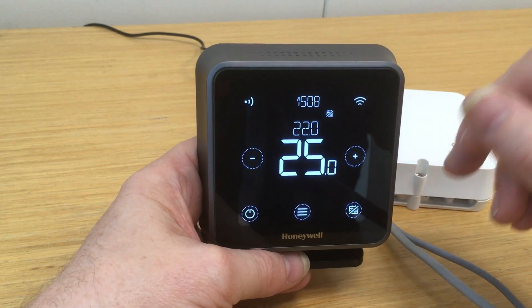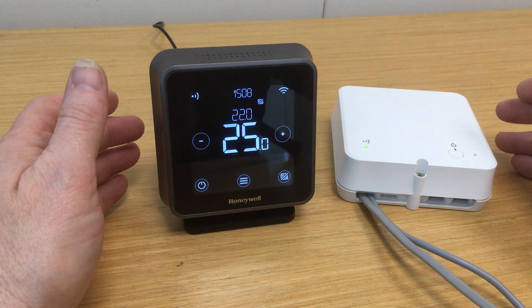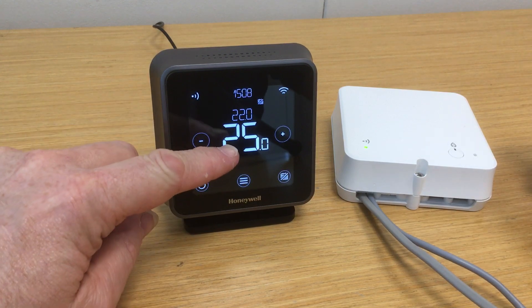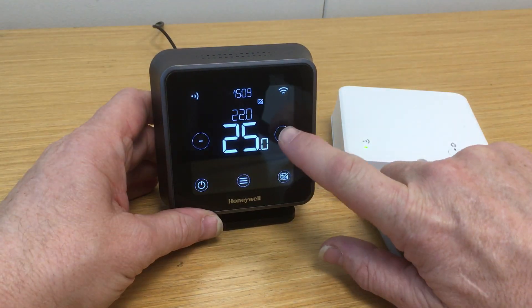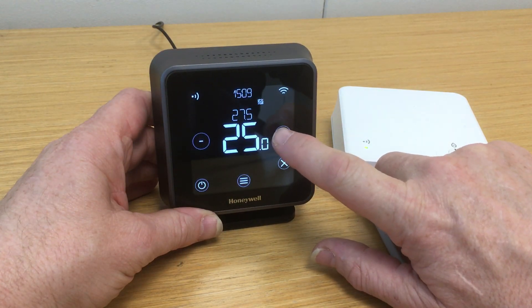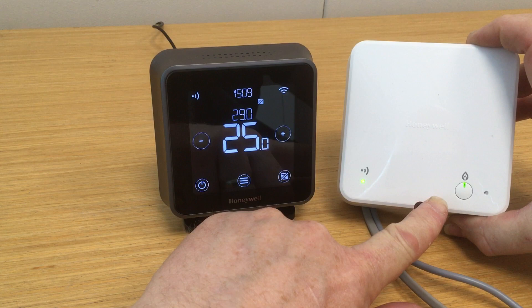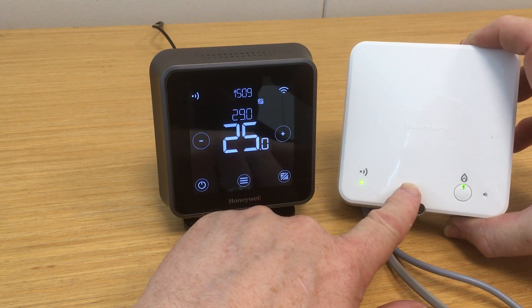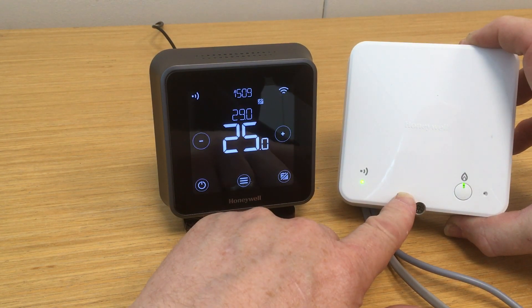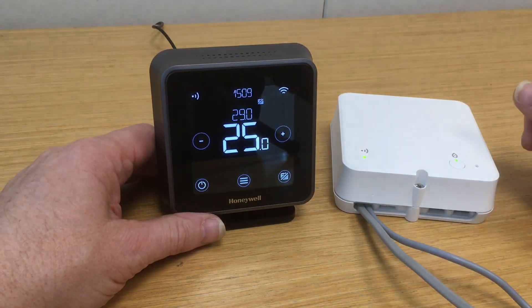And there we have the settings and OpenTherm readout. To quickly show you the OpenTherm operation on the heating side — at the moment we have a room temperature of 25 degrees and a set point of 22. So let's create a demand for some heat. We'll increase the set point temperature to 29 degrees. The heat demand LED has now illuminated. Notice there is no clicking of the internal relays because they have been disabled, as noted before, when using this in OpenTherm mode. So the request has been sent to the relay box, which is now communicating with the boiler via the OpenTherm bus.